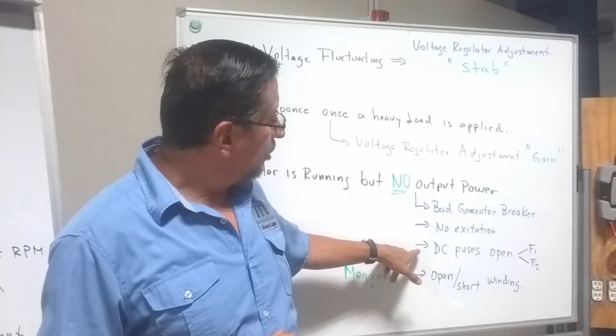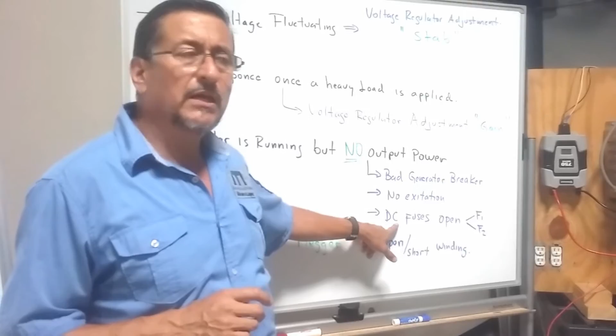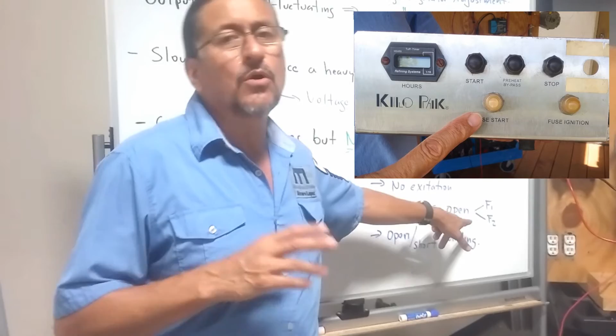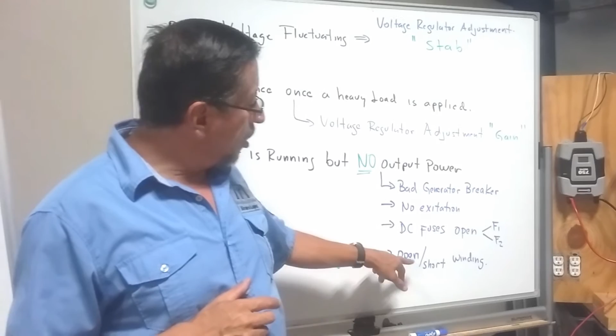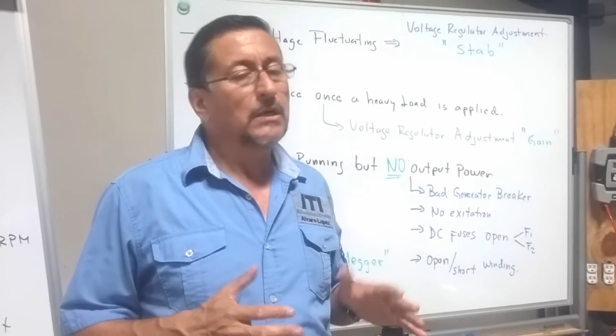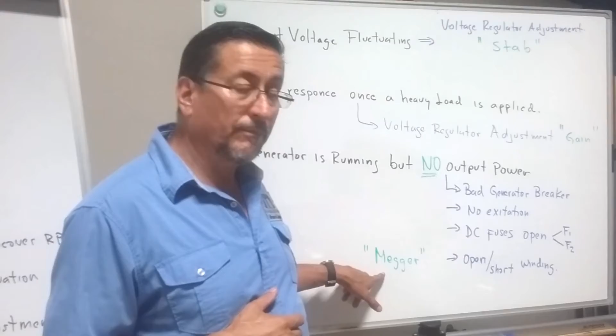Probably the bridge of diodes is damaged and no DC current, no AC current is produced. In that case, you need to replace the bridge of diodes. Another possibility is the fuses on the control box are broken. Normally, the majority of generators have 2 or 3 fuses, F1, F2, or F3. You need to check the fuses. Another possibility is an open or short on the winding of the stator and the winding of the rotor. This is basically a procedure that you can verify with the megohmmeter.